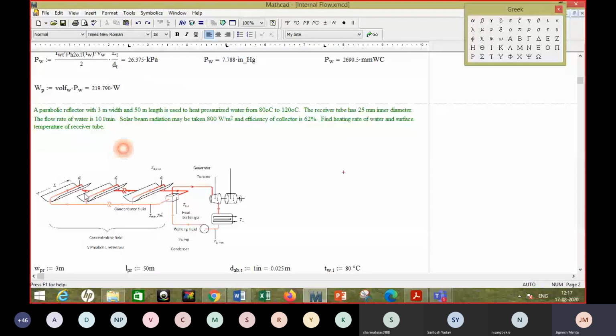So you could see the troughs, the parabolic trough, which work as reflectors, right? They are like mirrors because they reflect, but they need not be made up of glass. They are generally made up of aluminium sheets, which are highly polished for good reflectivity. And they focus it on the receiver tube, through which either the oil or water may be passed. Let's say in this case, we are talking about passing the oil through this tube. And the solar radiation is focused on this tube, and the thermic fluid temperature increases, and it's in a closed circuit, and there is a heat exchanger here.